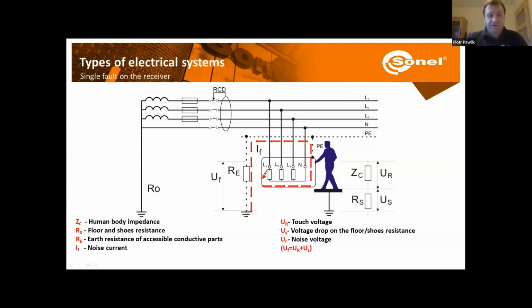So what are the dangers in this situation? Well, we can face some overheating leading to a fire. Or if the person is touching, then they will get an electric shock, and in the worst scenario, they can die. So we want to avoid it, and for this reason, we automatically disconnect the power supply in case of a fault. And for that reason, we can use RCDs, we can use MCBs, or we can use some bigger circuit breakers, for example, directly at the transformer station.